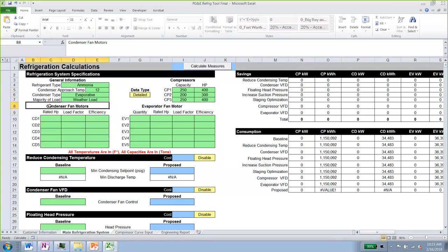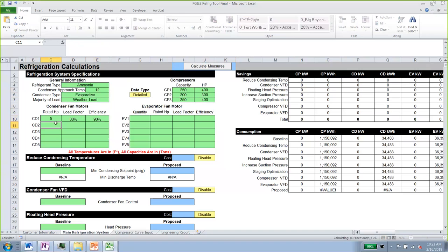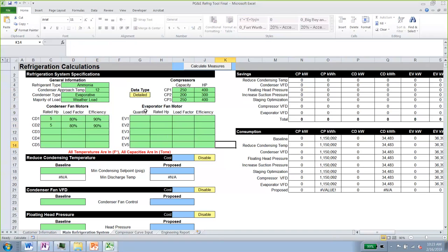Next, we define the condenser fan motors — we have two, each at five horsepower, with a load factor of 80% and efficiency of 90%. For the evaporators, we have 10 total fans split into two types: one is five horsepower and the other is six horsepower, with five fans of each type. The load factor is the same as the condenser.